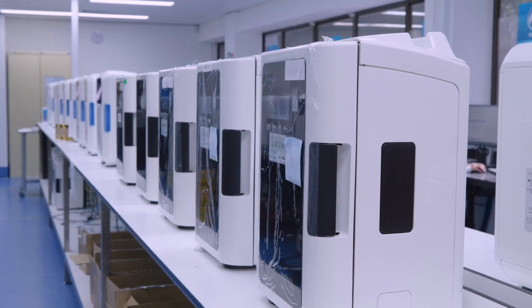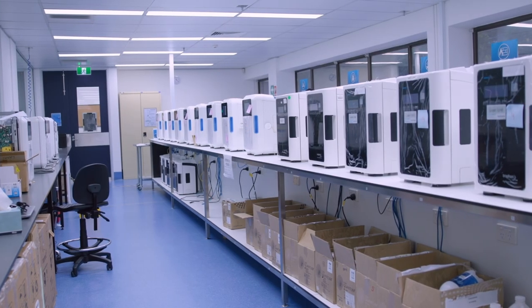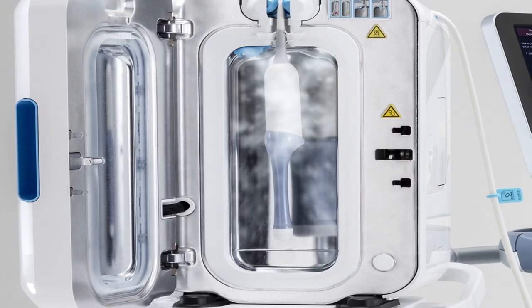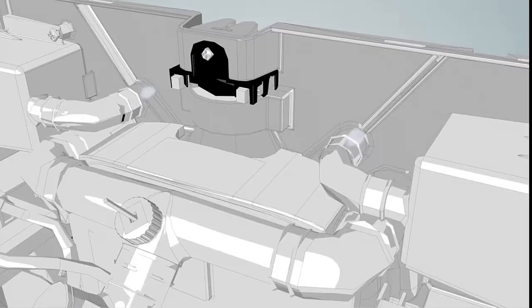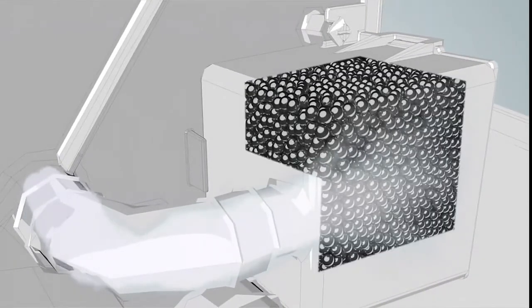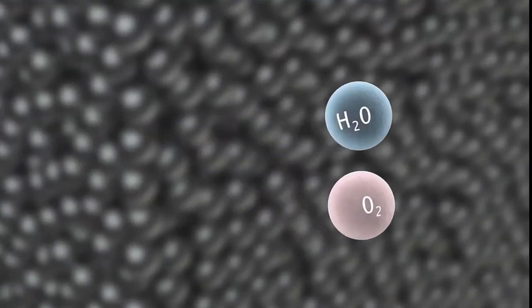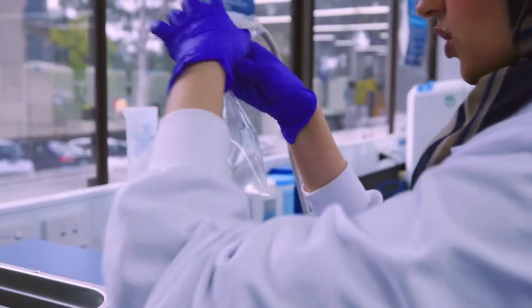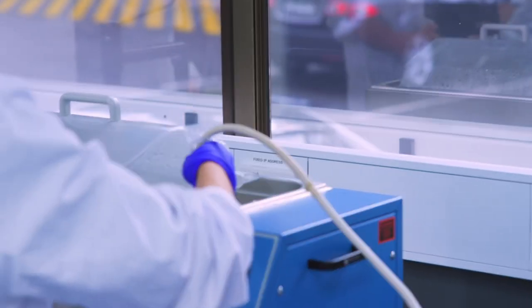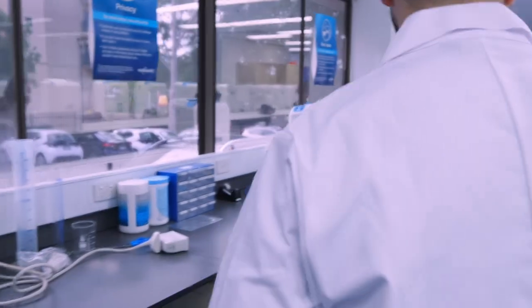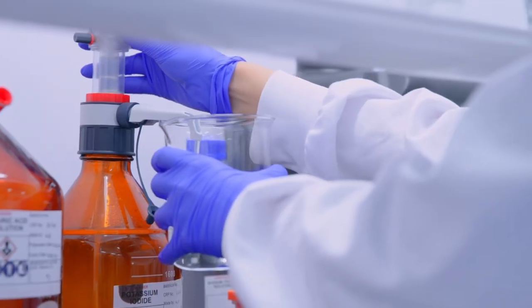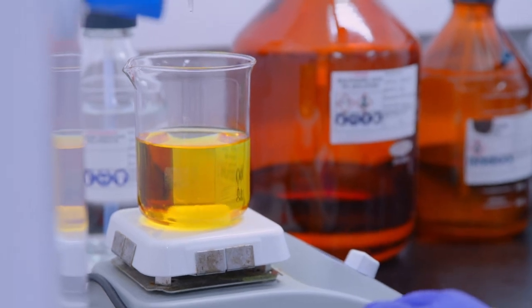Welcome to the lab. First of all, we run a standard cycle on a probe. We use minimal chemistry. It's a couple of grams only in each cycle, and then the device itself runs the exhaust process to take out all the mist from the system before the doors are open, and then the exhaust product goes to a catalytic reaction to break down hydrogen peroxide to water and oxygen. And then we take the probe immediately inside DI water. We extract the residual left on the probes using the water bath, and then we take that extract to another of our labs to analyze and calculate the amount of residual.